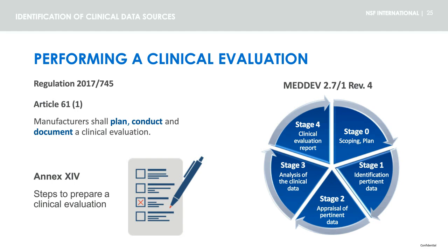However, not all the detailed steps are described there. In this sense, until a revised version of the MEDDEV 2.7/1 Revision 4 is prepared or other guidance is published, you might consider adopting in your internal clinical evaluation procedure the recommendations found in this guideline.